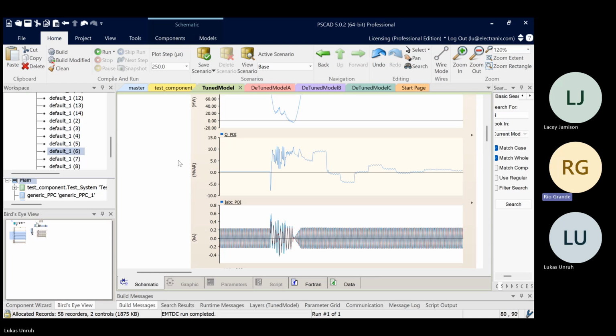Not necessarily, I guess. We would try to avoid them, if possible, and we might mark them in our model quality testing. But I wouldn't necessarily fail a plant on this in this context. If there was a system study done, then this might be a good hint to look closely at this specific fault type in a system study, and see whether it does this and whether it causes any problems.